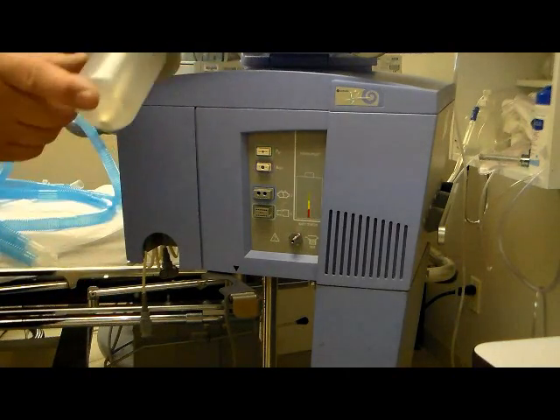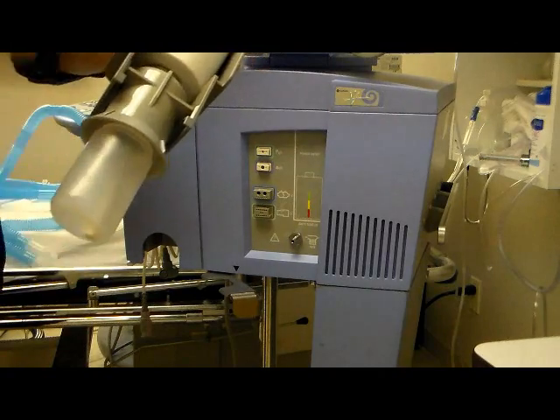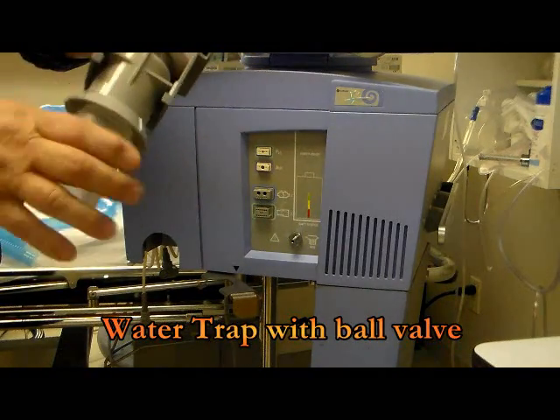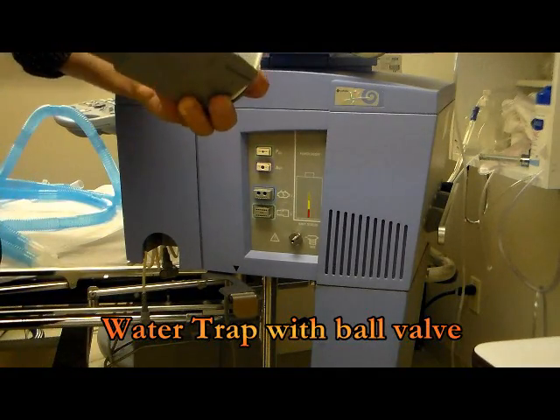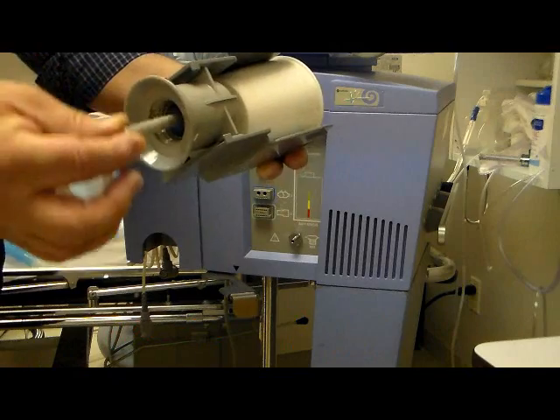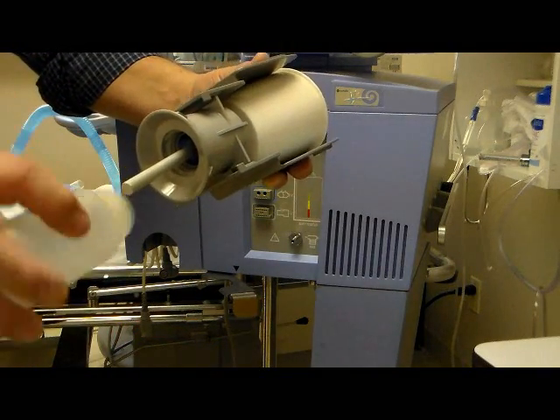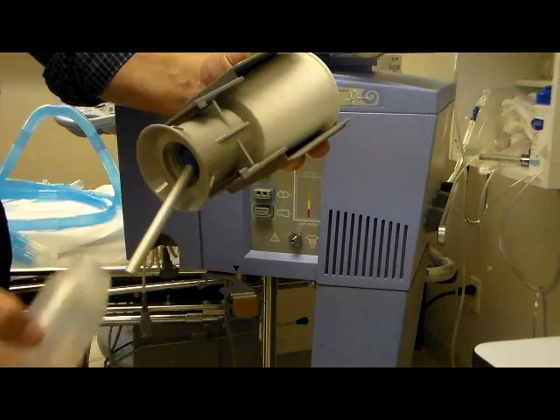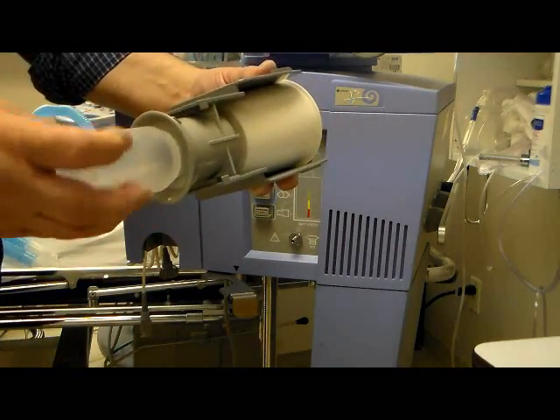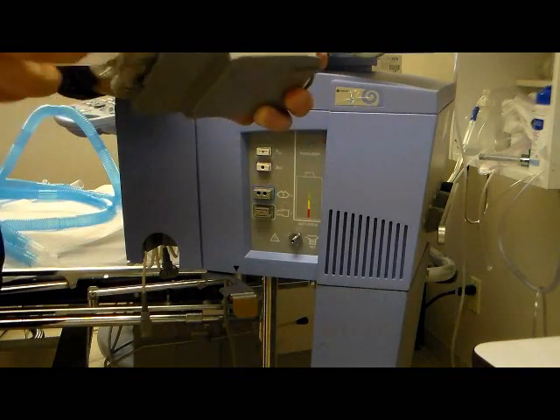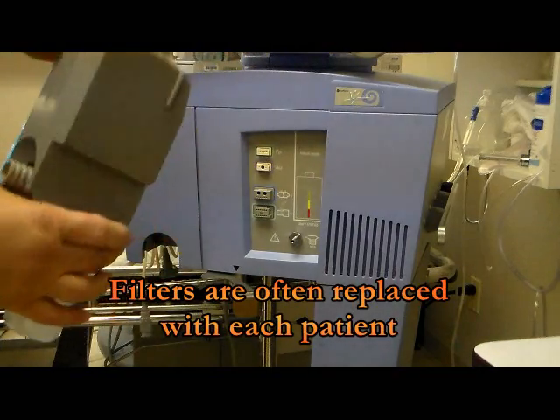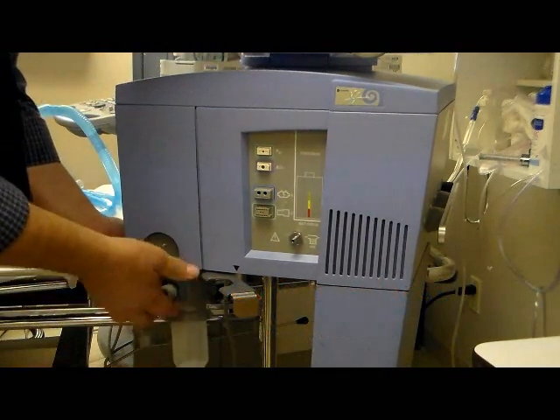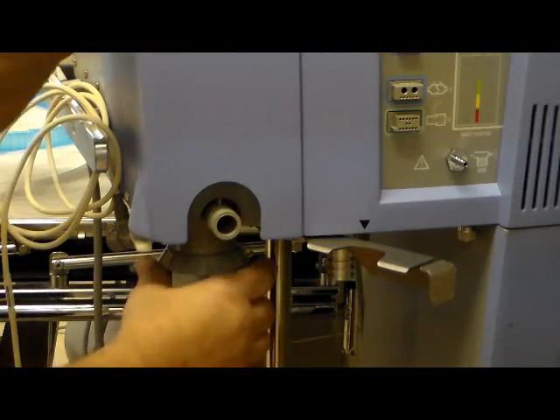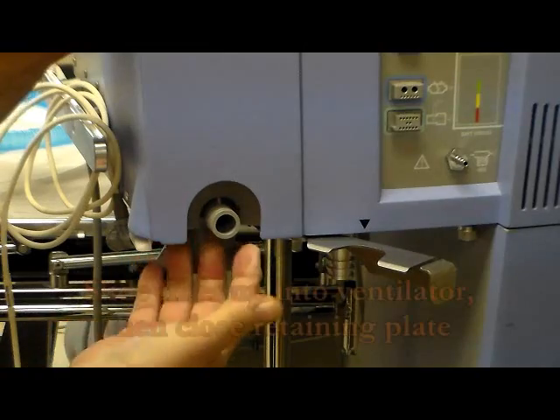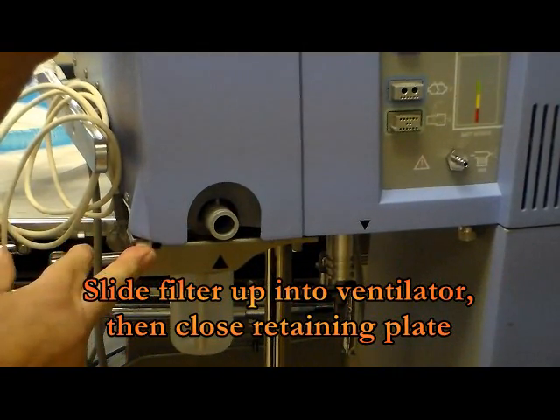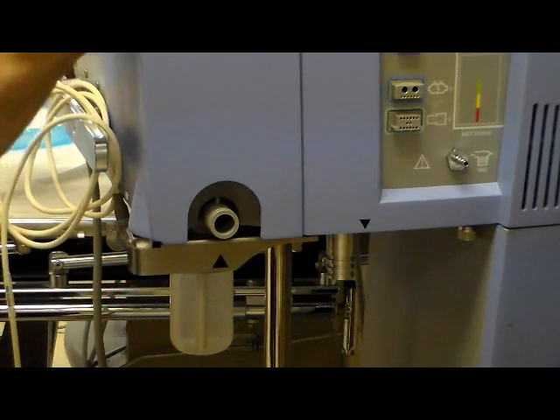Also, you have a small water trap down here, which can be unscrewed if you have a lot of rainout, and that allows you to drain it away. And in here is a little ball valve, which allows you to take the cup off without losing gas while it's in use. That goes back on, screw it in place, make sure you don't screw up the threads, and then this goes in here, slides up, locks in place, and make sure that you have this pushed up into the machine and that the latch can hold it from dropping out.